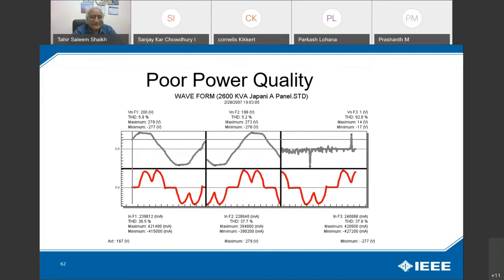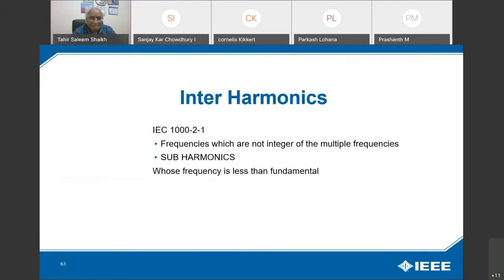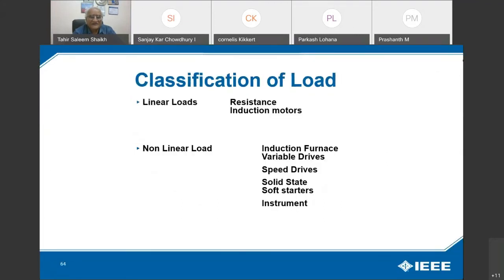This is very high. Normally, as per global standards, it should not be more than 10%. If the environment is very critical for power electronics equipment, it should not be more than 5%. I also see other frequencies which are not integer multiples of the fundamental. They are called subharmonics, whose frequency is less than the fundamental. We will not discuss interharmonics in this presentation, but they also create problems.